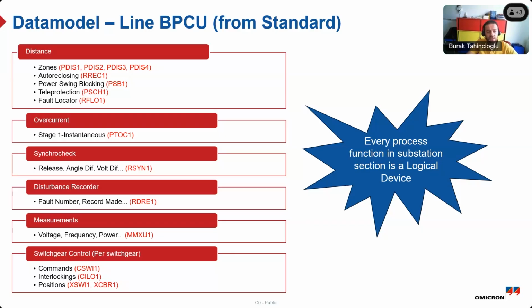And we would have some functions, as you see here, some protection functions, as well as some control functions. Okay, so you might be familiar with the logical nodes mentioned here. So we would have some distance protection, overcurrent, so synchro check. It doesn't have to be a protection or control function. Maybe a measurement is also a function, and you would also have in your substation a disturbance recorder. Maybe that would all be, whatever defined in the standard as a logical node is a function, what you define in the specification. Okay, we will utilize all these logical nodes.